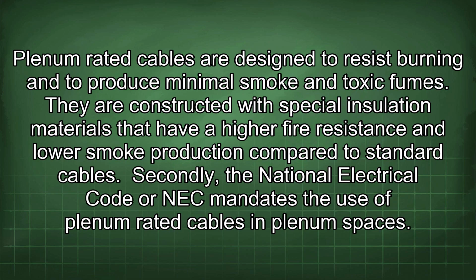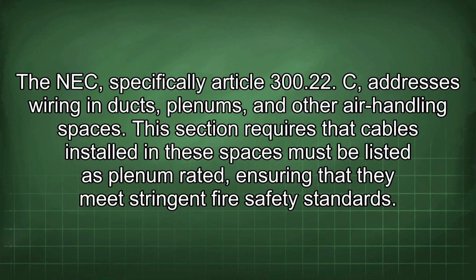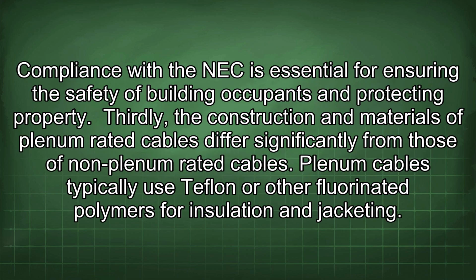Secondly, the National Electrical Code, or NEC, mandates the use of plenum-rated cables in plenum spaces. The NEC, specifically Article 300.22(C), addresses wiring in ducts, plenums, and other air handling spaces. This section requires that cables installed in these spaces must be listed as plenum-rated, ensuring that they meet stringent fire safety standards. Compliance with the NEC is essential for ensuring the safety of building occupants and protecting property.